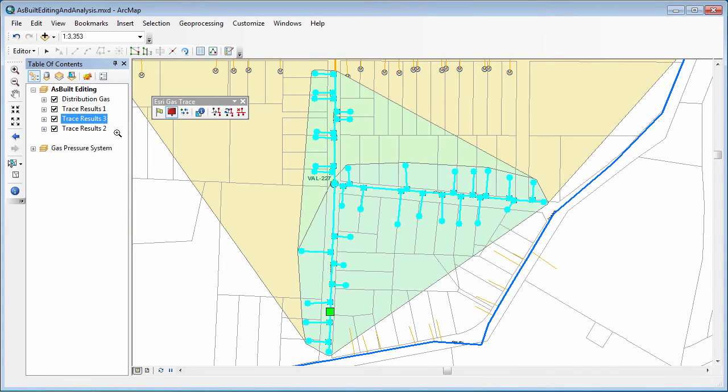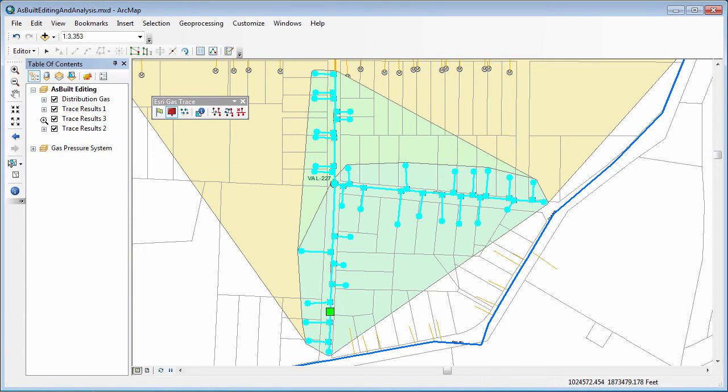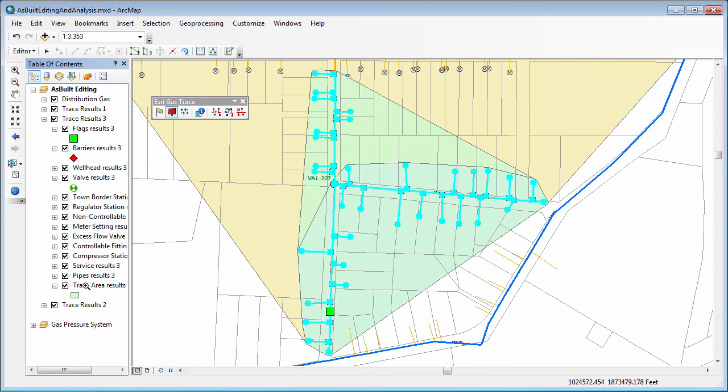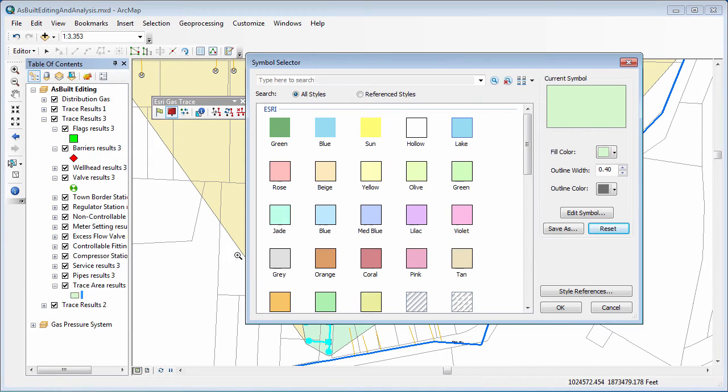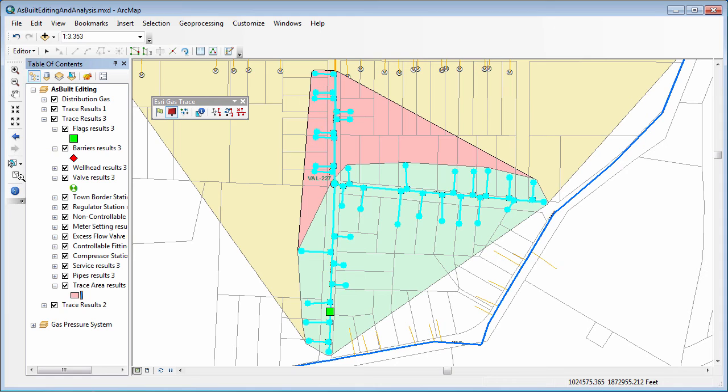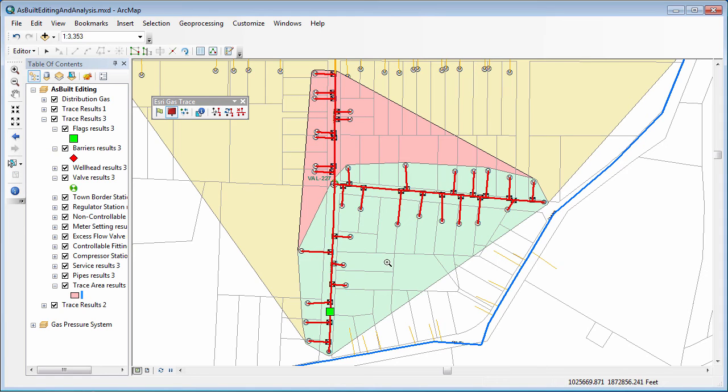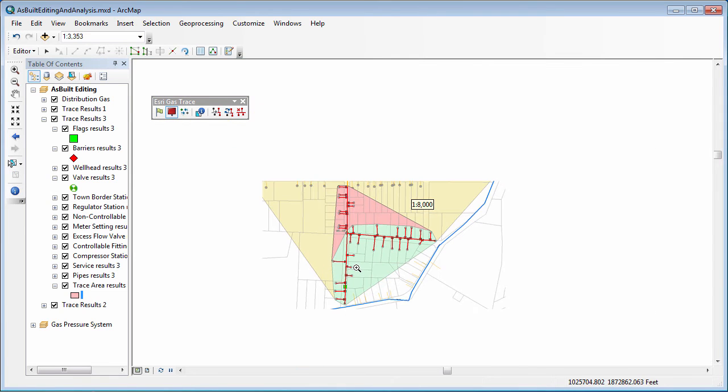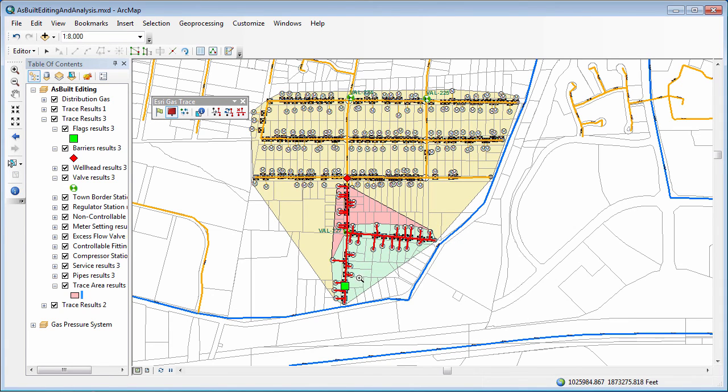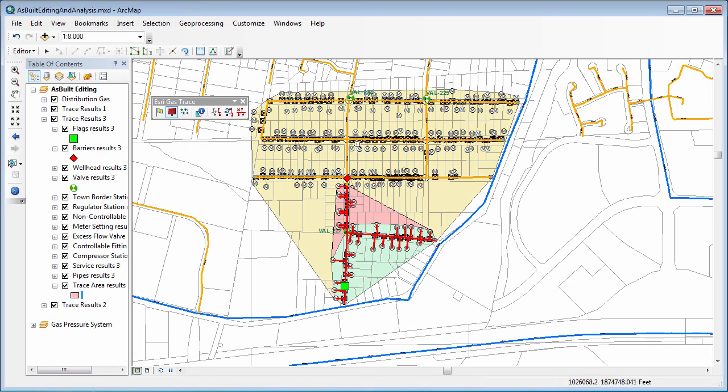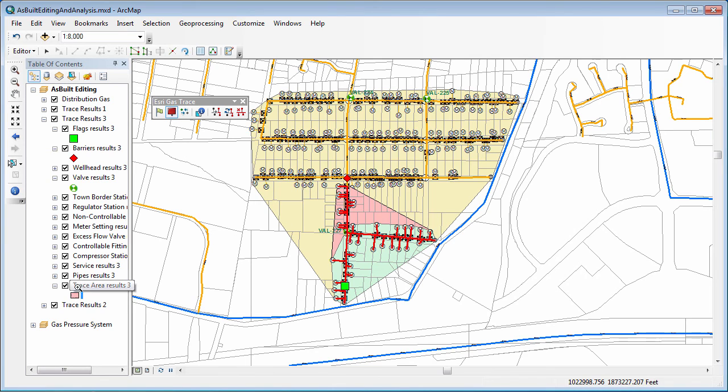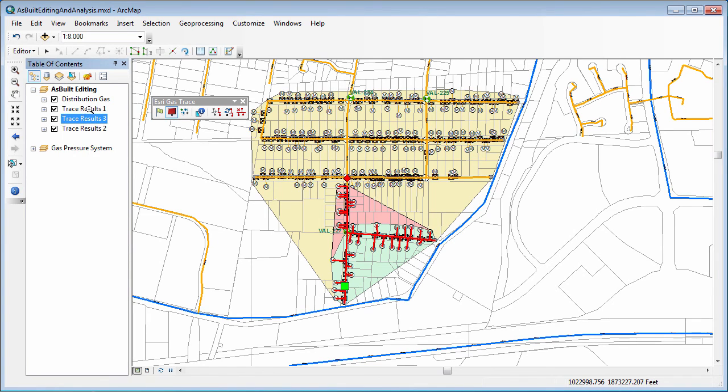We see yet a third set of trace results shown on the map here. Since I dropped those in between the two there, we might even go in and change the coloration there on number three to be a slightly distinct color, let's just say rose. You can see that a little bit more clearly. So you can see now on the map, I'll zoom out, the very first area, which was the green area, very small. We then of course marked that valve as inoperable and it found two additional valves up here on the northern side. But then we placed a squeeze on this pipe here and you can see that it got an intermediate point with those trace results here shown in the pink color. And I can rearrange these any way I want to if I want to bring up trace results number three on top.